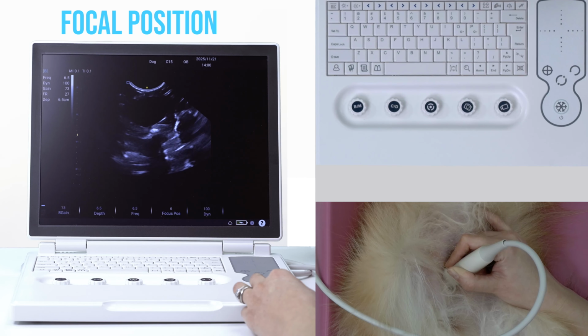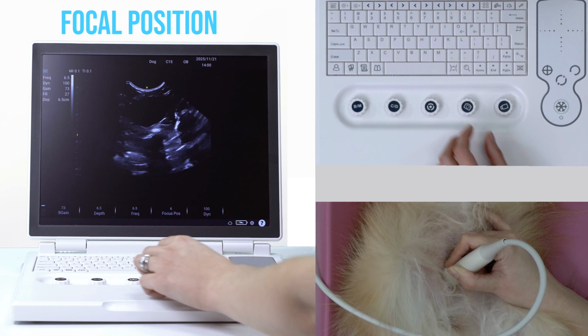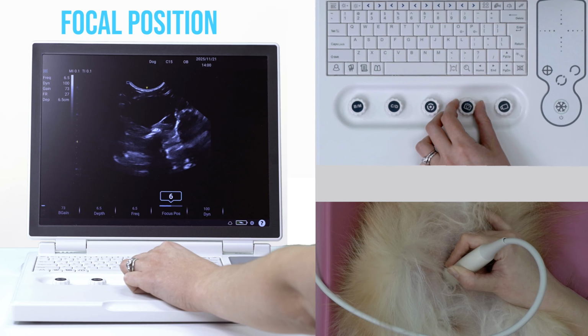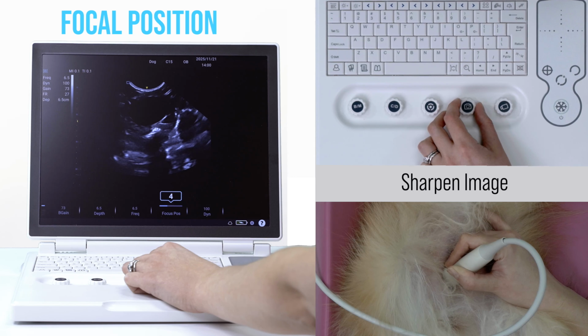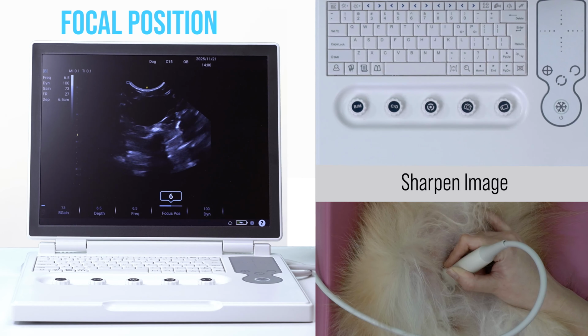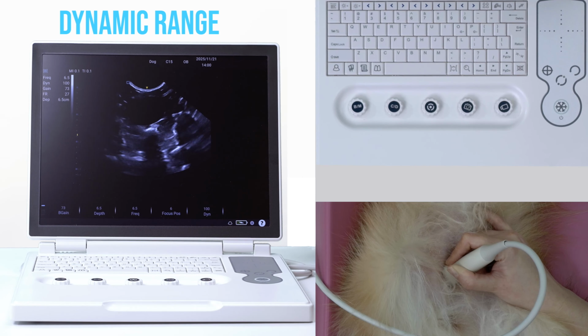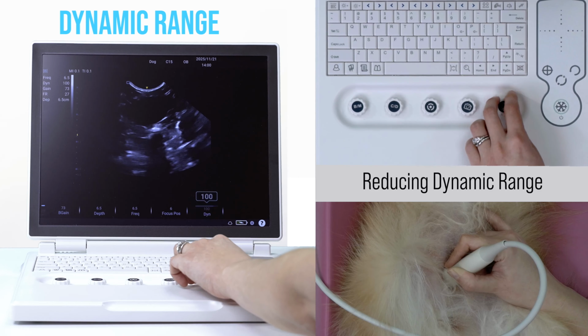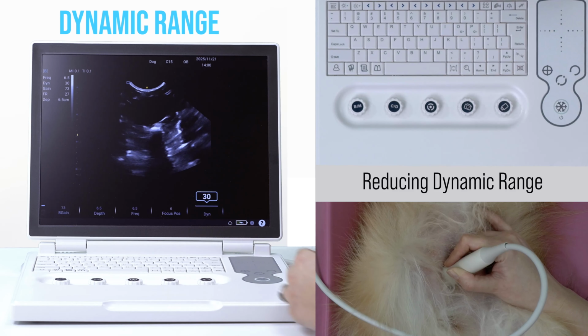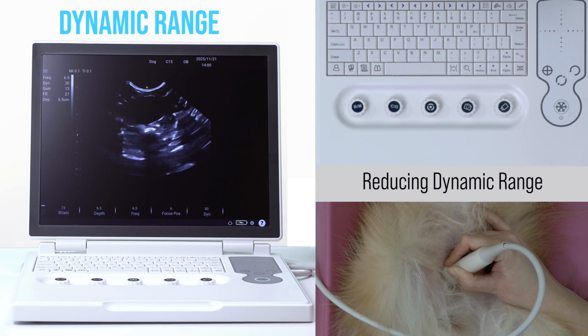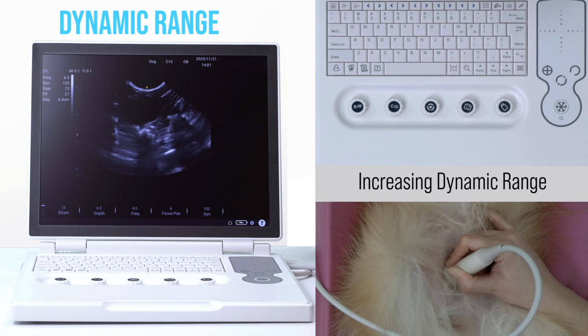Your focal position is usually in the right place, which is roughly in the middle of your screen, but you can adjust this to sharpen up your image at the area that you are looking at if you need to. And dynamic range, which I mentioned earlier, you probably will not need to adjust, but let me just show you what it does. If I bring it all the way down, I get a high contrast image, and all the way up, I get a milkier looking image.